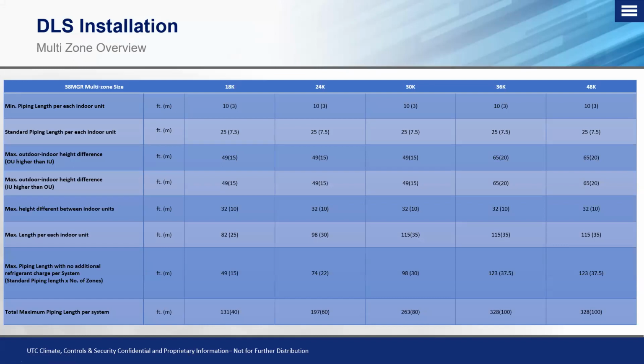And then finally, you can always reference your product data, your installation data, and your service manuals for all your information. Now, in this case, this is going to be your 38 MGR multi-zones, your 18, 24, 30, 36, and 48. It'll give you your minimum piping length, your standard piping length per each indoor unit, height differences that are allowable, maximum height differences, maximum length per each indoor unit, maximum piping length with no additional refrigerant charge, and then your total maximum piping length between all of your zones. This is where you're going to find all of your information as you're installing it to make sure that you're within the allowable limits. And of course, if for some odd reason you don't have this information, you can always call and ask, and that's what we're here for, to help you make sure that you are applying and installing the systems properly.